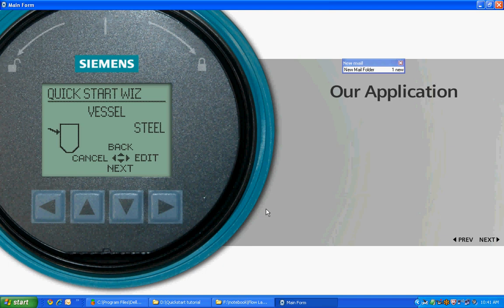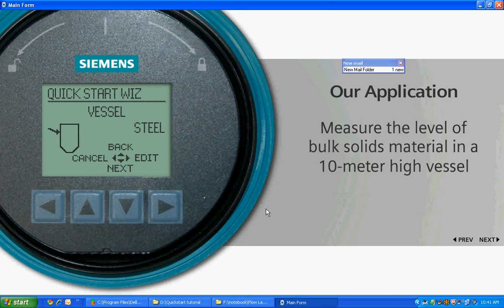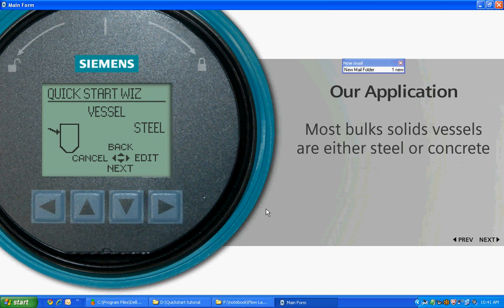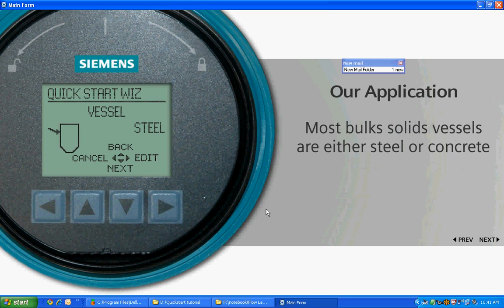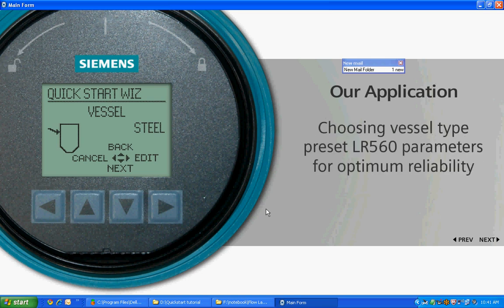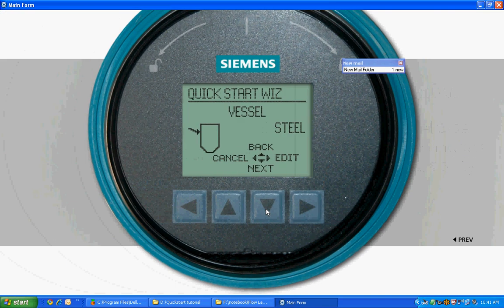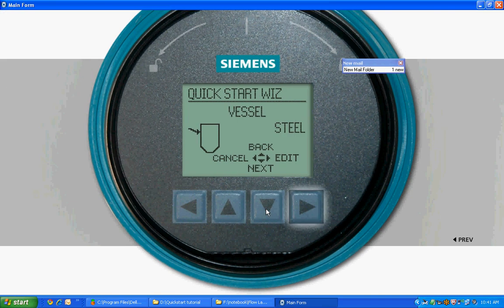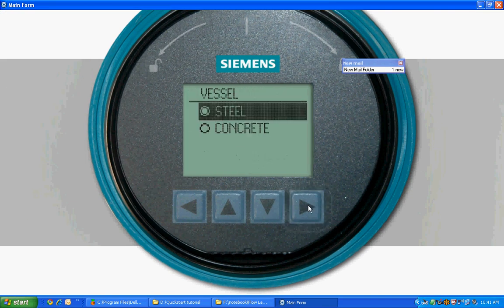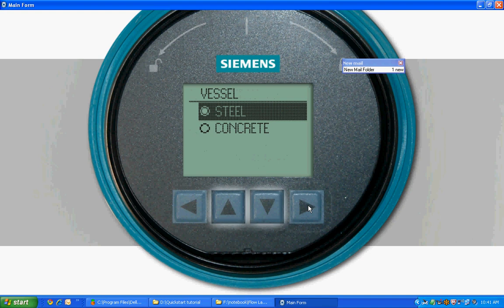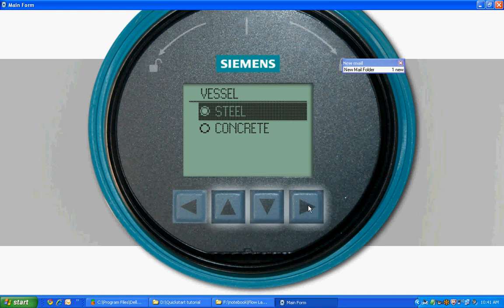In our application, we want to measure the level of bulk solids material in a 10 meter high vessel. Most bulk solid vessels are either steel or concrete. By choosing your vessel type, you preset the LR560 parameters for optimum reliability. Choose Edit to select your vessel type and use the up or down arrows to select your option of steel or concrete. Then right arrow to save your choice.